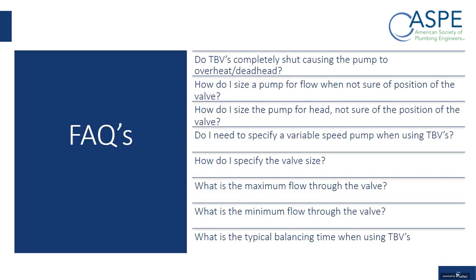So some of the frequently asked questions. Do thermostatic balancing valves completely shut? We already talked about that. No, they don't. They have a bypass in there. How do I size a pump for flow? We're not sure of the position of the valve. Sizing the pumps for heat loss has nothing to do with a thermostatic valve or any type of valve in there. It's based on the piping, the insulation, the size of the piping, and the length of the piping and the ambient temperature. So it has nothing to do with the balancing valve. So don't get concerned about where the valve is going to be position-wise when I have to size my pump.